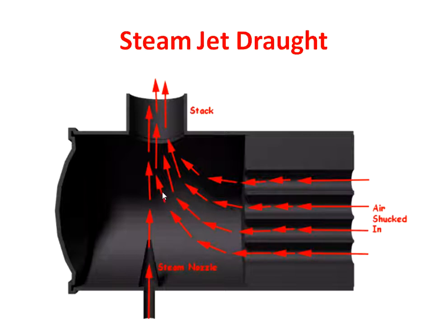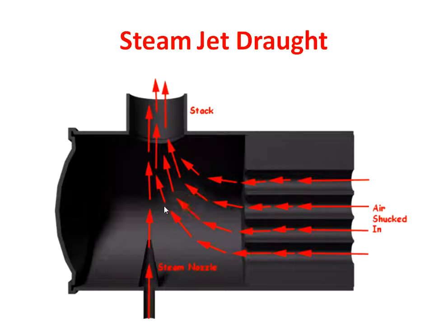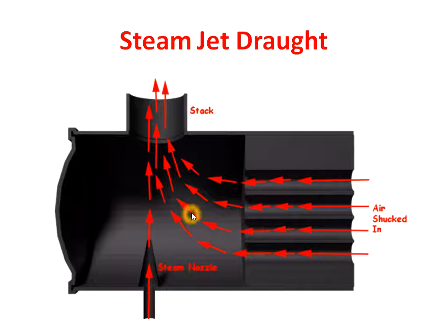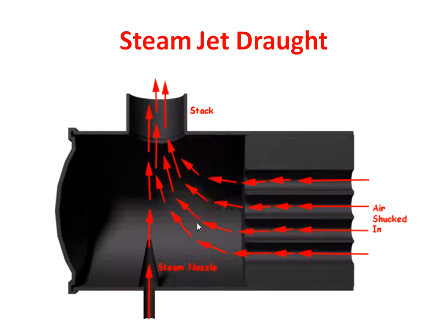So what happens when steam is spread in this section — due to steam pressure, this gas goes out into the atmosphere through this stack. And when this gas goes out through the stack, some negative pressure is generated in this chamber. Through this negative pressure, fresh atmospheric air is sucked inside this chamber.